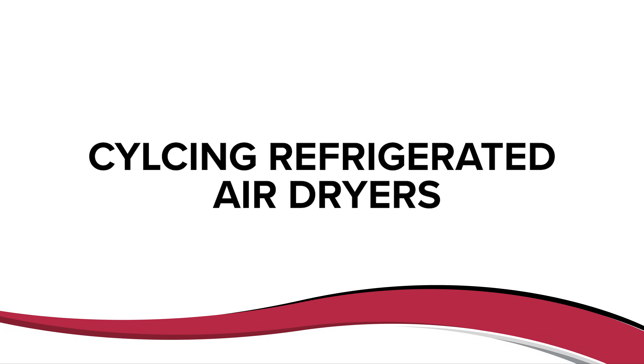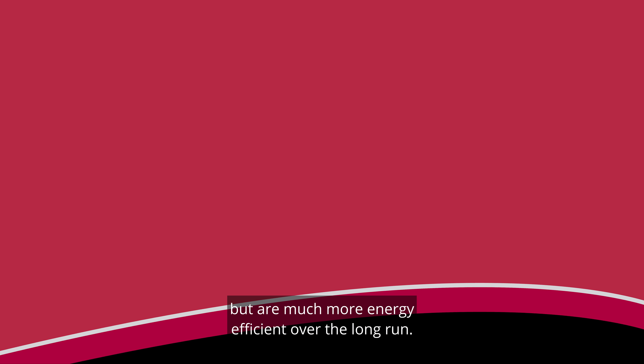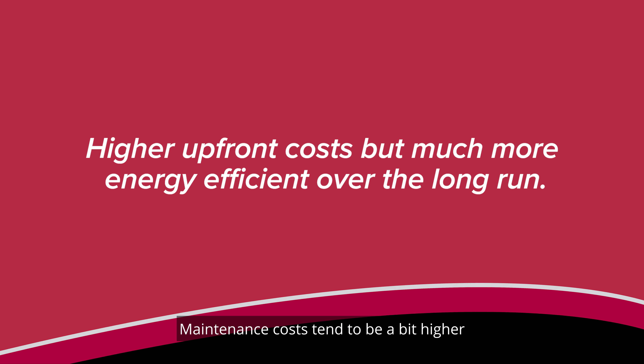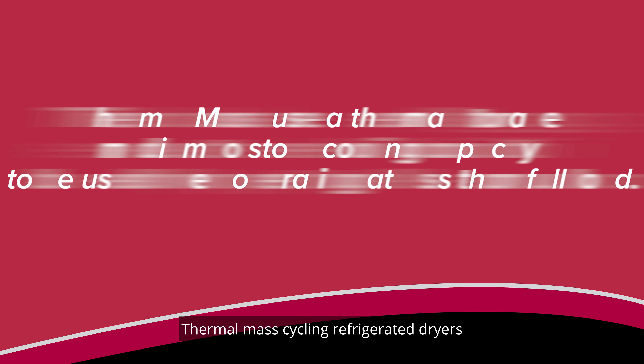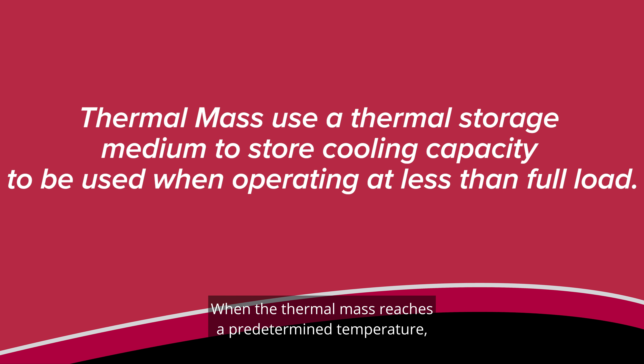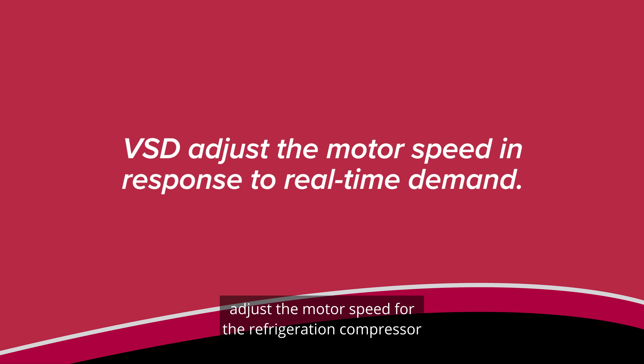A cycling refrigerated air dryer reduces energy by cycling on and off in response to demand. These dryers cost a bit more upfront, but are much more energy efficient over the long run. Maintenance costs tend to be a bit higher than for non-cycling refrigerated dryers due to their increased complexity. There are three types of cycling refrigerated compressed air dryers. Thermal mass cycling dryers use a thermal storage medium to store cooling capacity for use at less than full load. Digital scroll cycling dryers cycle the refrigeration compressor on and off in response to demand — either operating at full capacity or no capacity. Variable speed drive refrigerated air dryers adjust the motor speed for the refrigeration compressor and condenser fan in response to real-time demand.